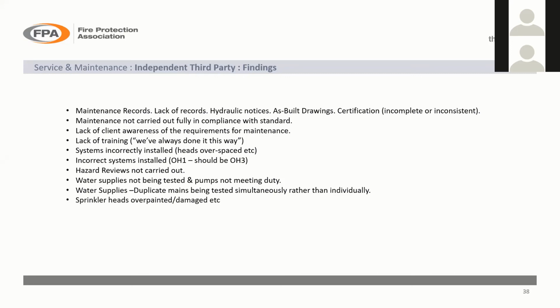So things like that, you've got to be checking for that kind of thing. But if you get any kind of paint on the sprinkler head, then that sprinkler head should be replaced immediately, and that should be picked up on a hazard review on a quarterly basis. We've been to premises where the usage has changed, and they've changed from office to TV studios in some areas. We've got storage methods which have been changed.